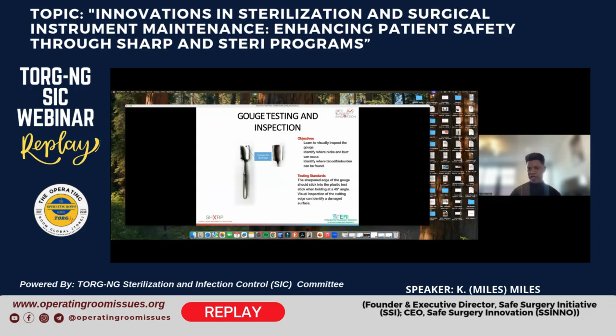And that's the same when it comes to inspecting surgical instruments. Once you learn the basics of how to inspect surgical instruments, you'll be able to inspect any type of surgical instrument, regardless of whether it was in this list or not, just based off how the instrument is used and how it's designed. So based off the design of the instrument and the usage, you're able to take that information and analyze any type of surgical instrument and know how to inspect it based off those different parameters.